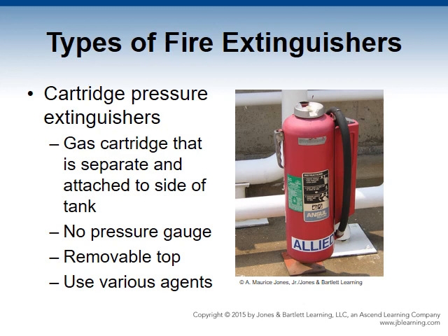Cartridge pressure extinguishers are similar to stored pressure extinguishers, but the gas is stored in a separate cartridge attached to the side of the tank. When activated, it punctures the cartridge and the gas is expelled into the tank, forcing the agent out. Because the cartridge is sealed, there is no need for a pressure gauge, but there is a lack of constant pressure. The top can be removed without dumping the agent or losing pressure, facilitating easy maintenance. It uses loaded stream, foam, dry chemical, and dry powder agents.